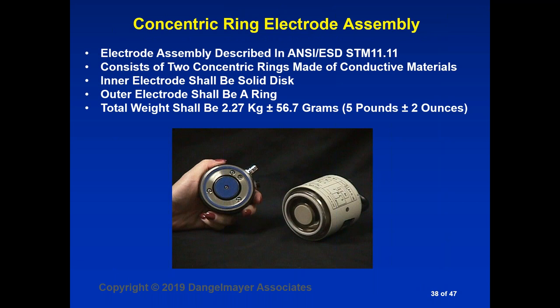So here's a picture of our concentric ring assembly. It's described in STM 11.11. It consists of two concentric rings. The inner ring is a solid disc, and the outer electrode is actually a ring. And once again, these things should weigh at least 5 pounds to get the proper pressure on the surface.